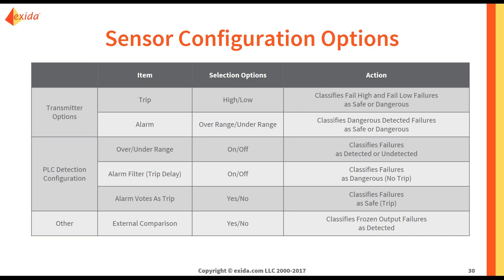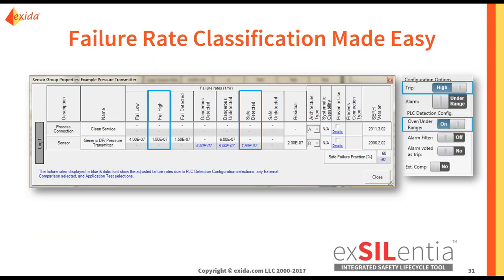So this is how exSILentia helps you to classify your failure rates. Let's go back to our sample problem. Starting with the fail high failures — you can see the blue box around the fail high black failure rate. In this case we have said it is a high trip, that the alarm is driving the signal under range, and that the PLC is detecting any over or under range signals. This means that your fail high trips the plant, so it is a safe failure. And since your PLC is detecting any over or under range signals, it is detected. So you see that 1.5e-7 is applied to the safe detected area. If you had selected off for over or under range detection, meaning your PLC cannot detect any out of range signals, this would be under the safe undetected category.